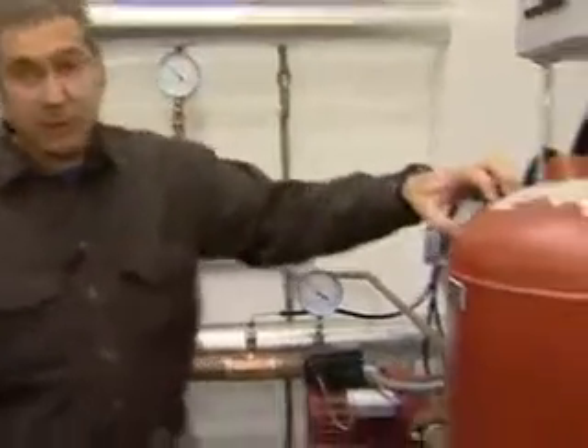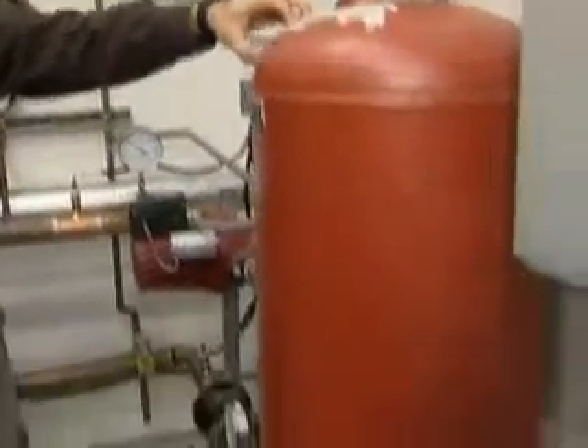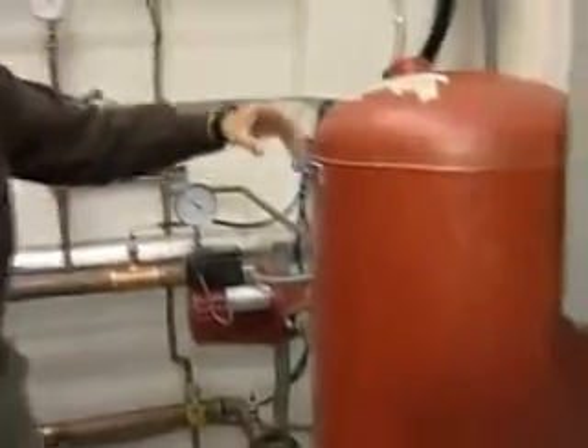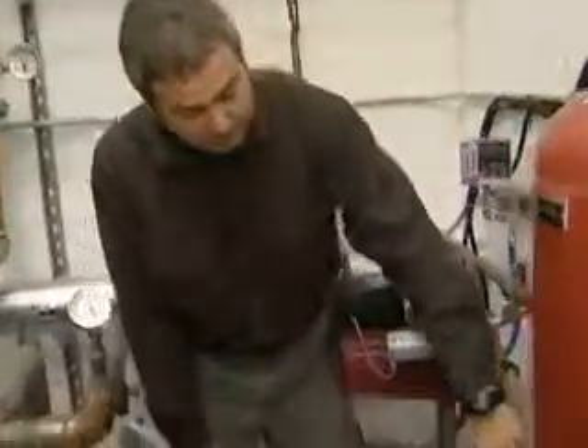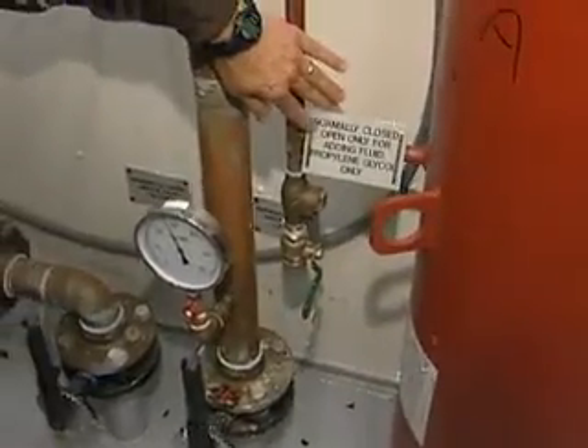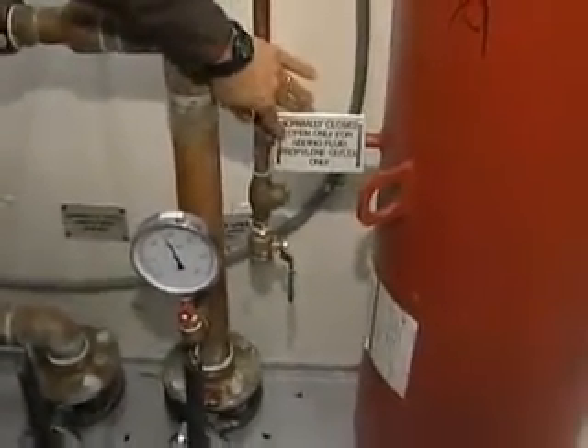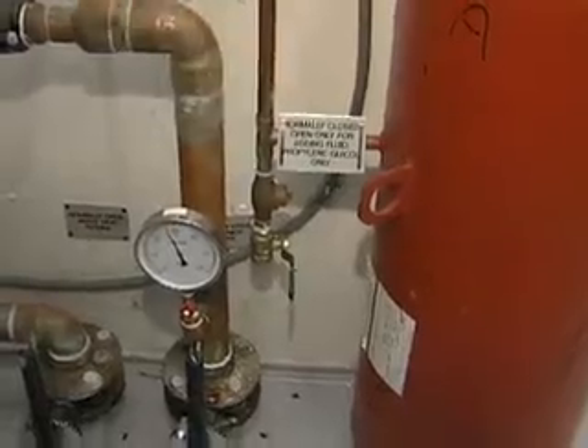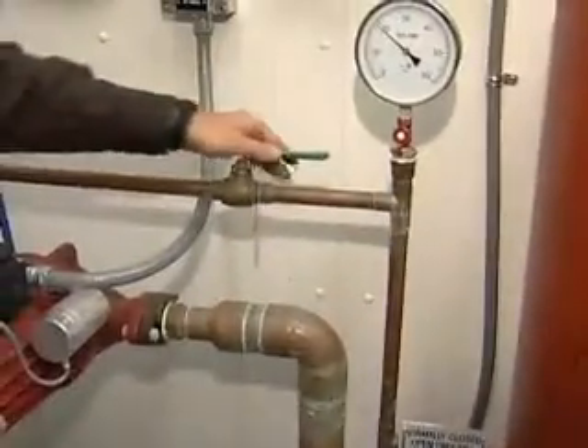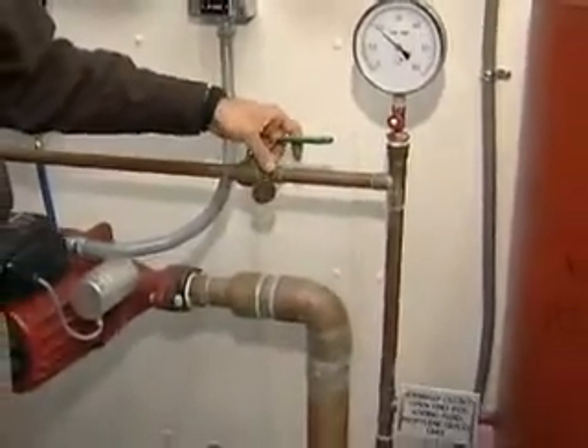Now this system, because it operates at a higher pressure, has a closed expansion tank. So this expansion tank does not have a sight gauge on it. Over here we have a valve, which is our add point. And it's a different colored valve tag. It says normally closed, open only for adding fluid, propylene glycol only. Because this system goes outside the building, we use a different type of glycol, propylene glycol, that's non-toxic.